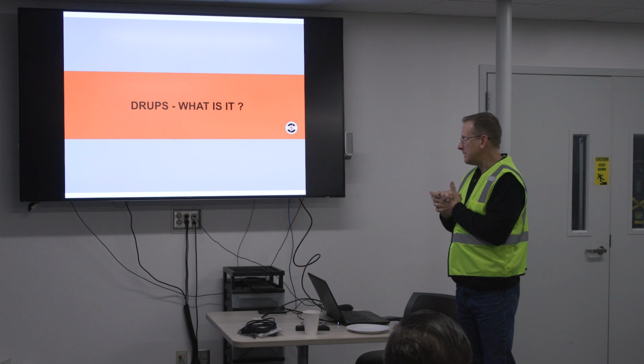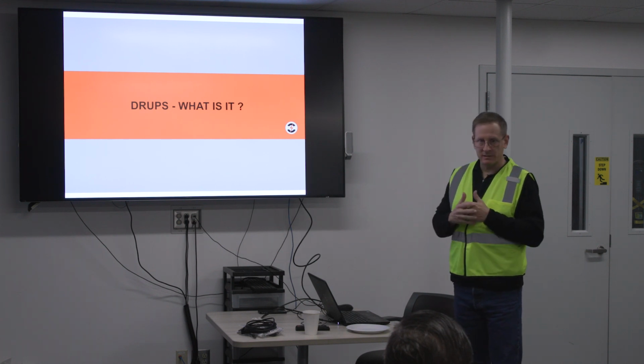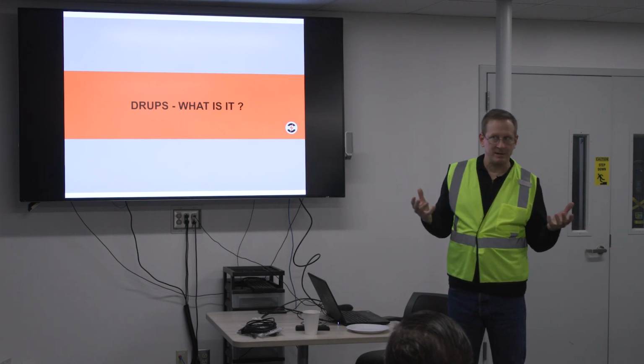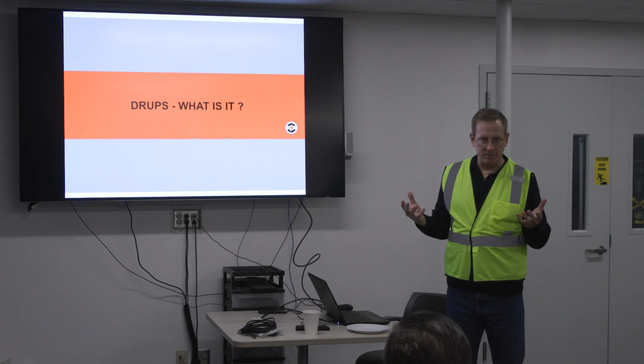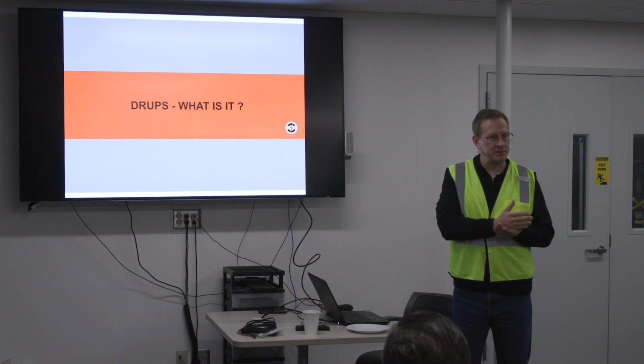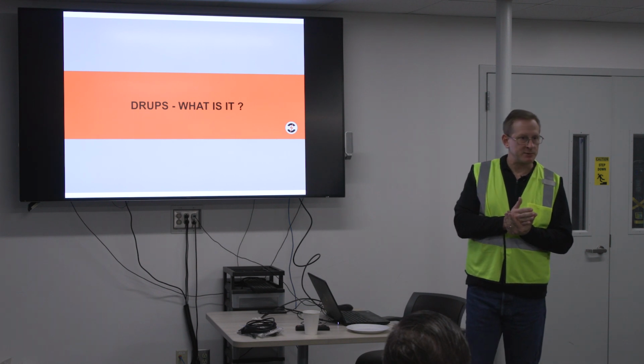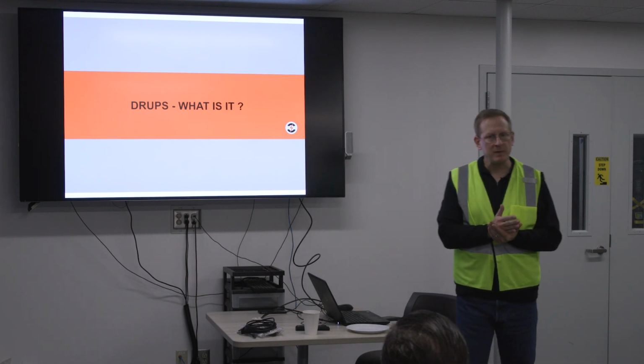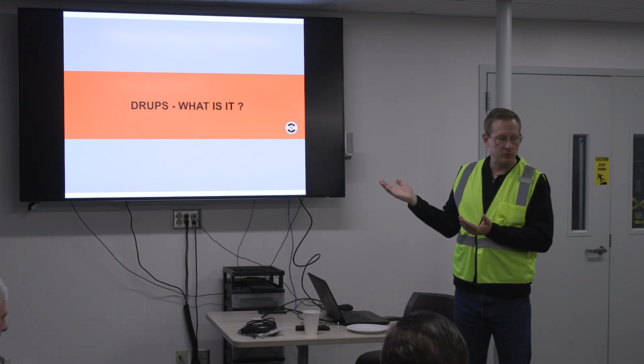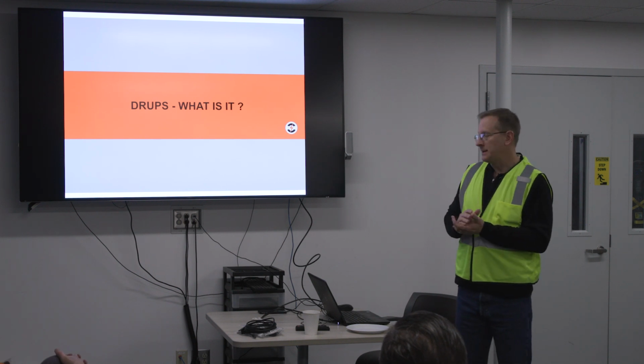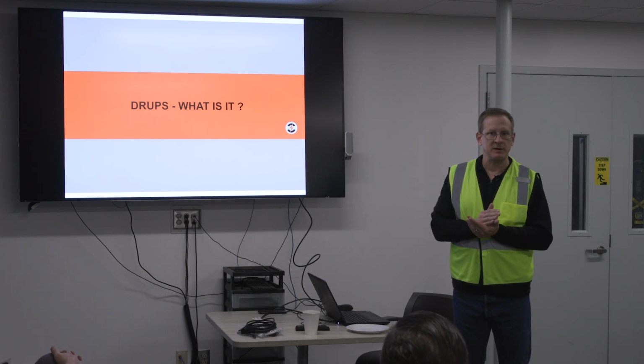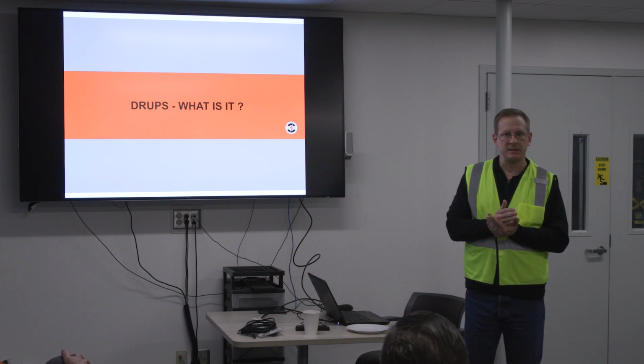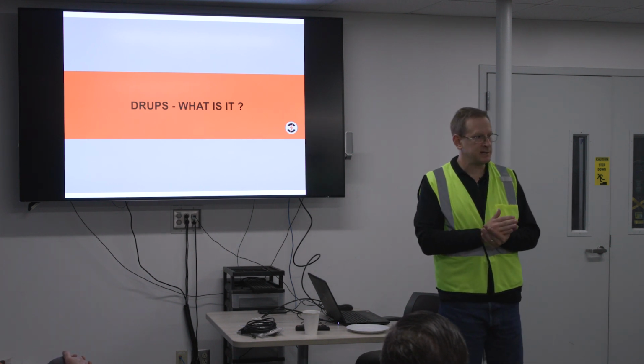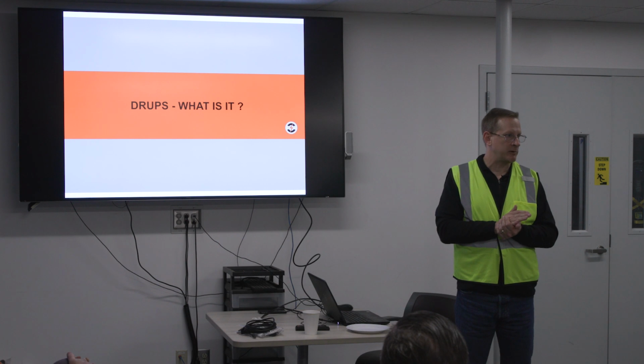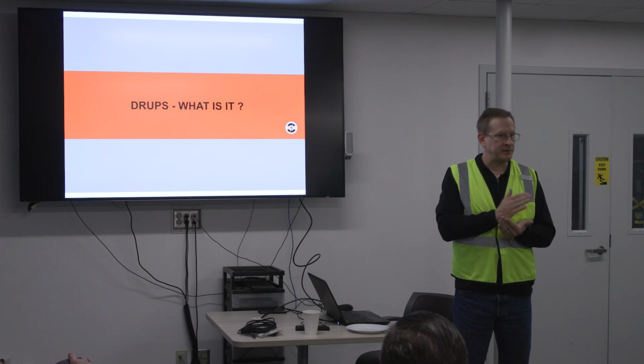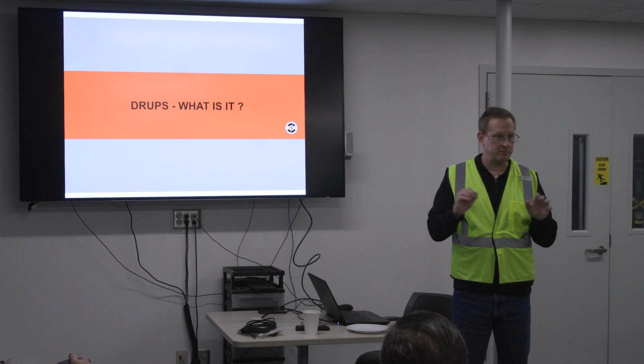What is a UPS system? Basically, it's a machine that is placed within your one-line distribution that's going to feed some sort of critical load. We'll see an actual one-line of that later on, but if the power goes out, if the utility goes away, if whatever is feeding the critical load ceases to exist, your UPS is going to basically sustain your power to your critical load throughout the duration of that outage. Okay, basically in a nutshell.